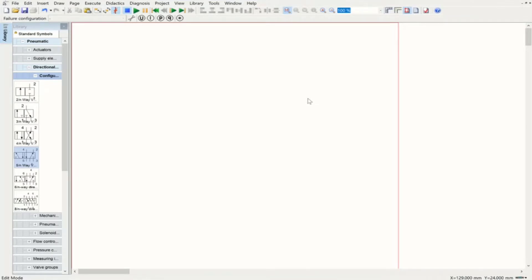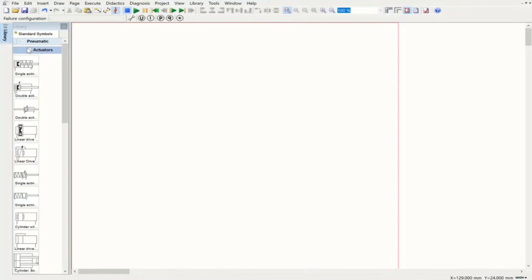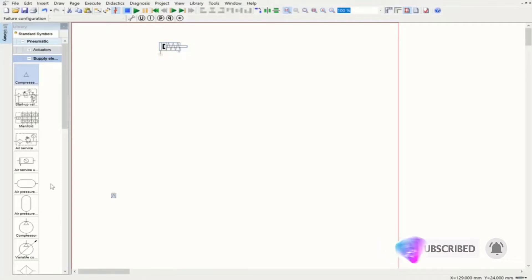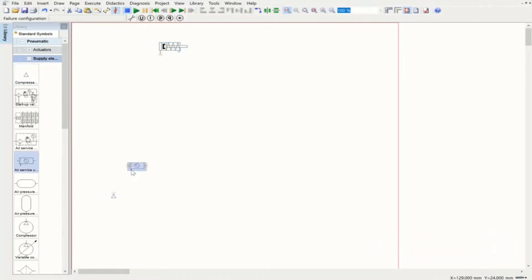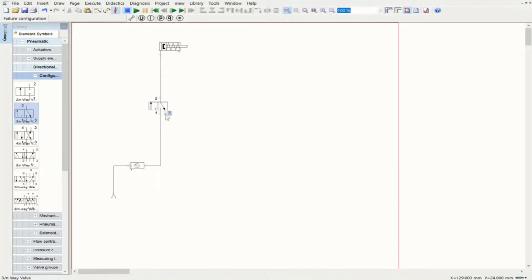The first circuit I'm going to design is direct control of a single acting cylinder, and then we'll modify the circuit with the use of a double acting cylinder. The first thing we need is a single acting cylinder, then a supply element — the compressed air supply and air service unit — connecting these two. The next component is a directional control valve configurable with three ports and two positions. Connecting all of them and putting the exhaust as well, this circuit is ready.